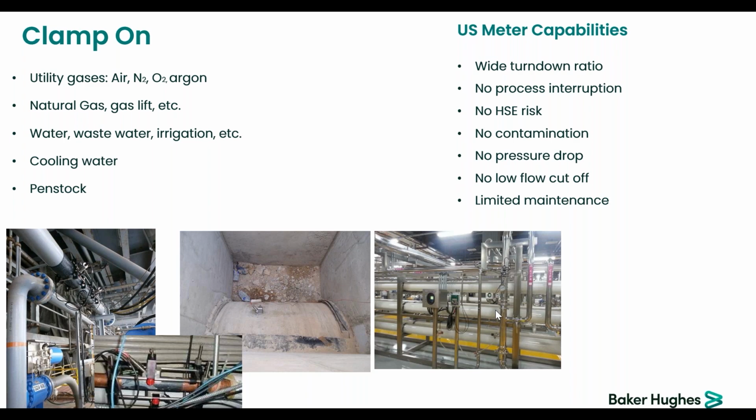So if it goes, let's take another example, well beyond this 40 Fahrenheit, let's say 100 plus Fahrenheit, then you will need to use a function that is called a tracking window, and you put it on because it can be off, which means that when the signal is no more captured, the window will start to move left and right to recapture the signal. But in case of a 40 degree Fahrenheit shift, it will stay within the window. Okay.